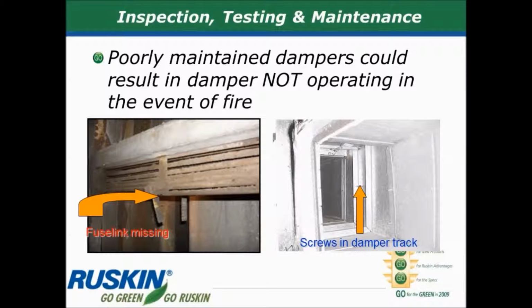The photograph on the right, you may not be able to see it clearly, but there are screws that have been put in the track of the damper frame, which is where the blades are supposed to travel. So if there ever was a fire and this damper wanted to close, it would get hung up on those screws and not be able to close and do its job.